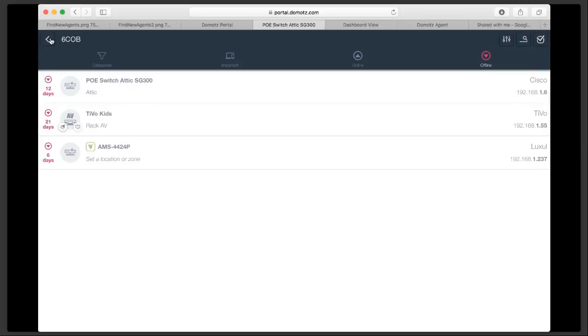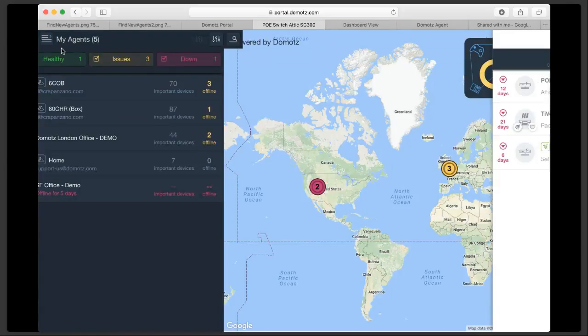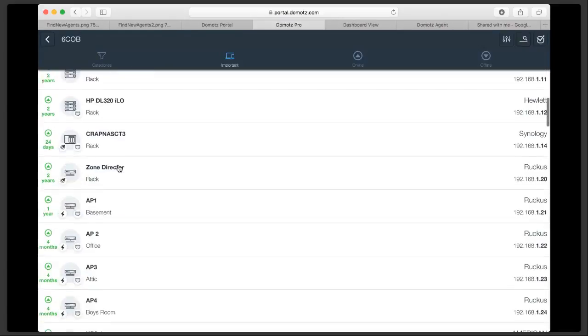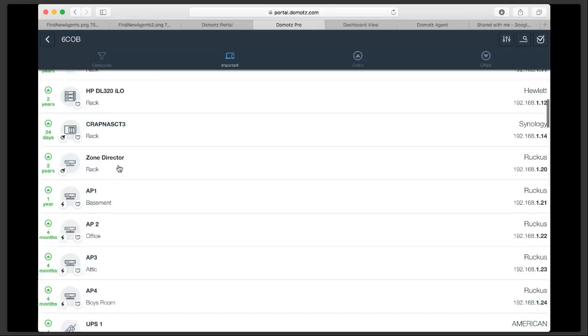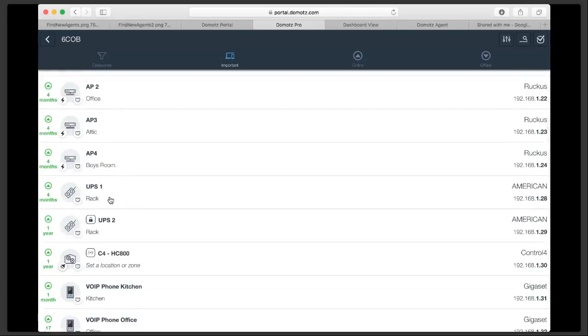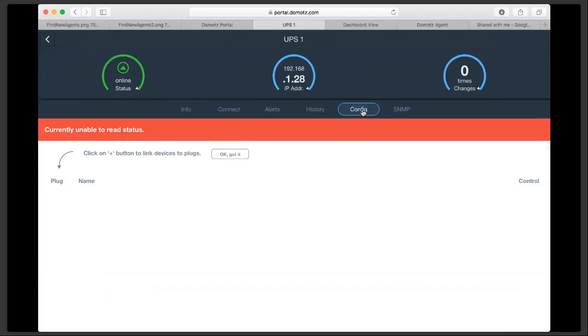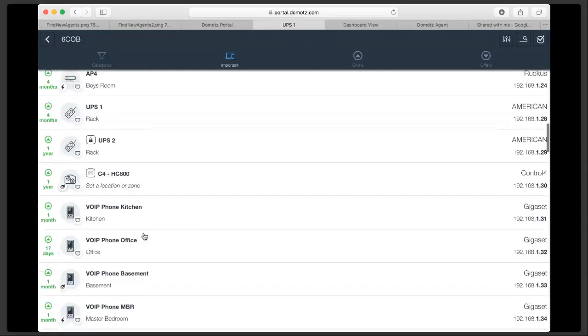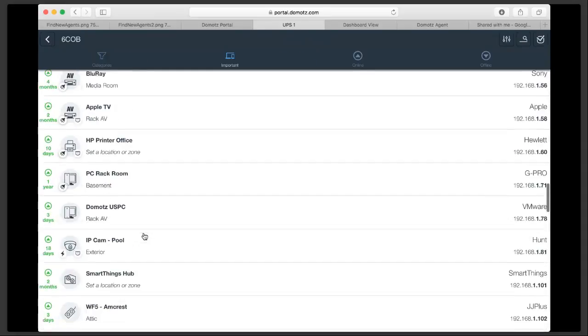Another thing I want to show you on the device list is the possibility to map devices on specific PDUs. If you have a PDU that you can control through IP, for example SnapAV, Wattbox, Digital Logger, or Middle Atlantic, and so on, all those PDUs can be remotely controlled by Domotz itself, in the same way you do when you are on site at your customer.